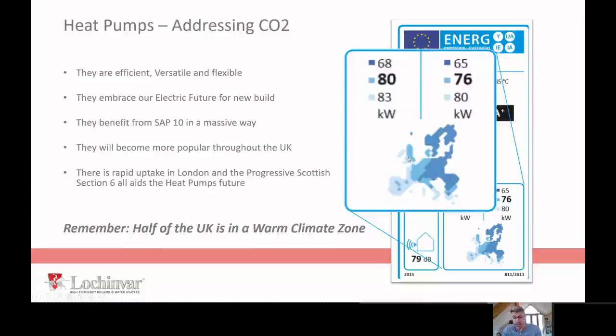If you're lucky enough to be in the south of the UK, you are in a climate zone that, for an air source heat pump, would be considered comparable to the outskirts of Spain. So not necessarily the nice holiday weather, but what we have got is a very stable climate. We don't get big peaks and troughs in outside air temperature. We're really steady, and the impact of that is, Ireland, south of the UK, just under East Anglia, so London, you're in there. It's a great place to install an electric heat pump in terms of its seasonal efficiency.